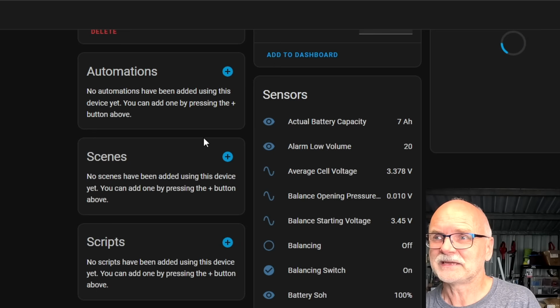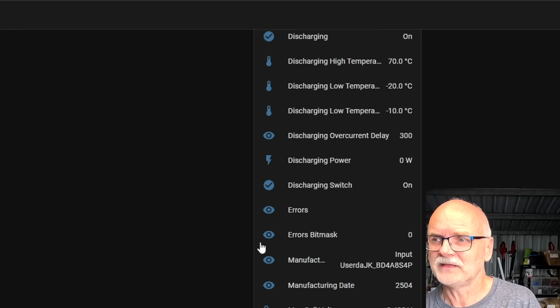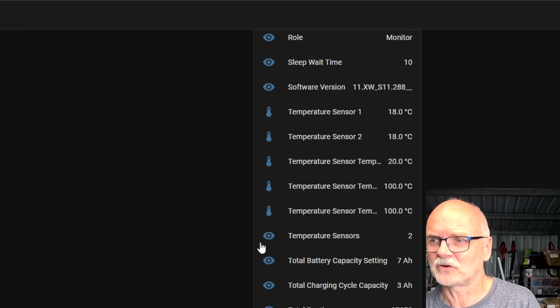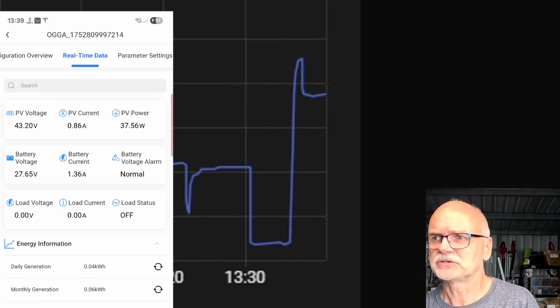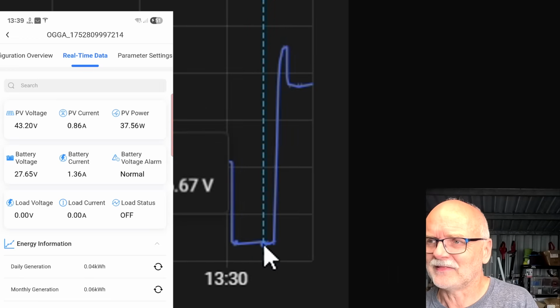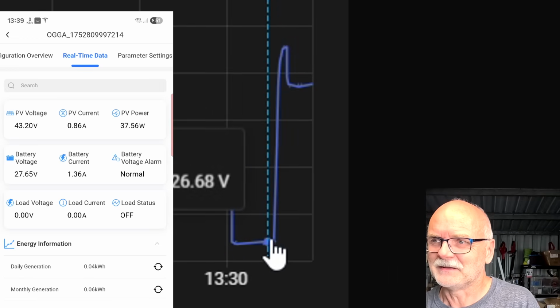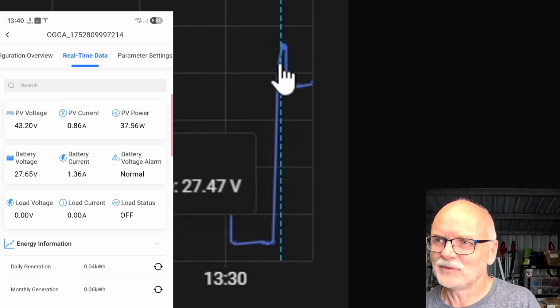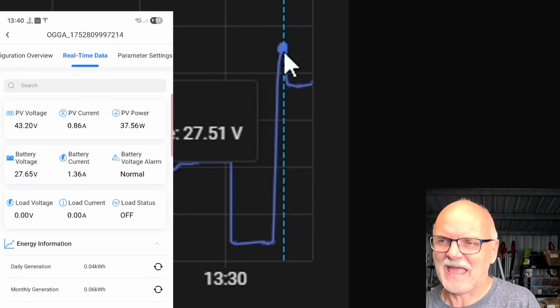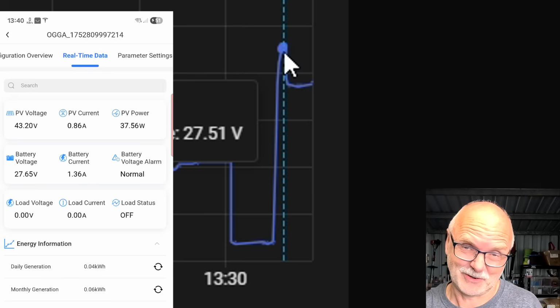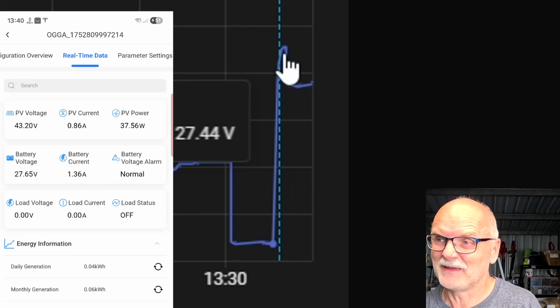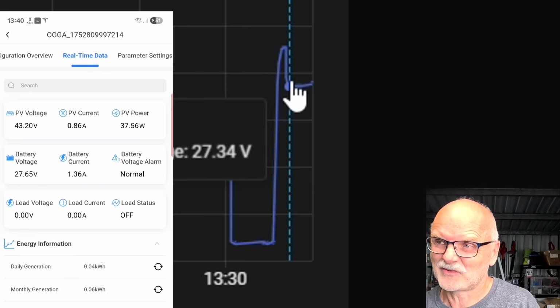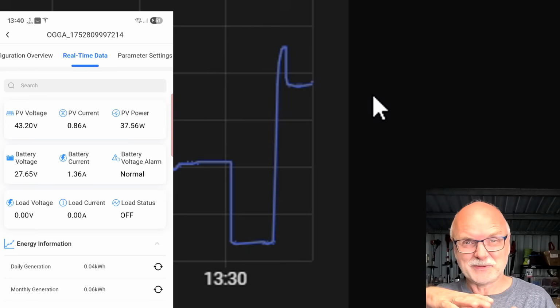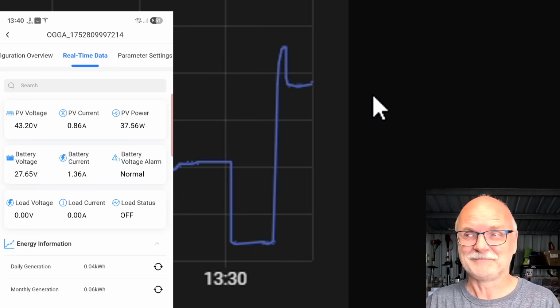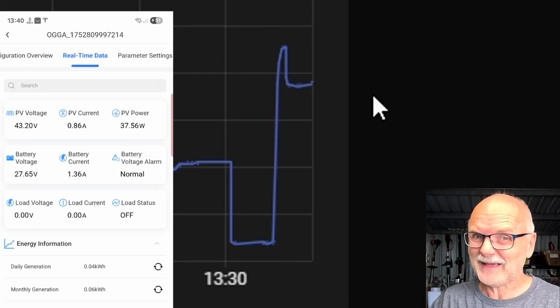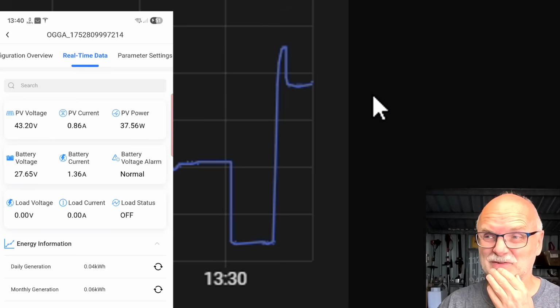We can probably see this in the IBMS monitor. Here, total voltage - you can see it at the end of the charge curve. This is our charge, and then we reached 28 volts, what the Solar Charge controller thinks. We're absorbing for a minute, and then we're dropping down to float now. Typical charge algorithm curve, right? So this seems to work quite well, actually, except the voltages don't match.